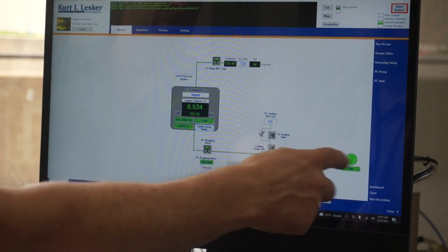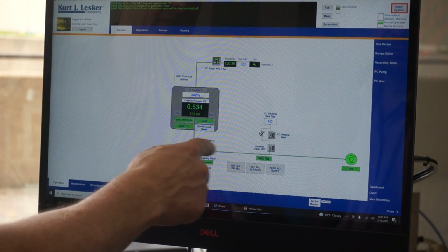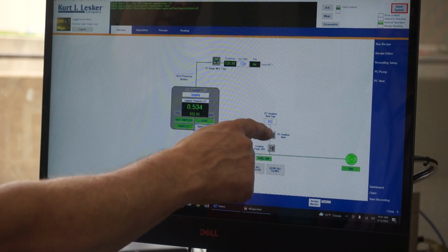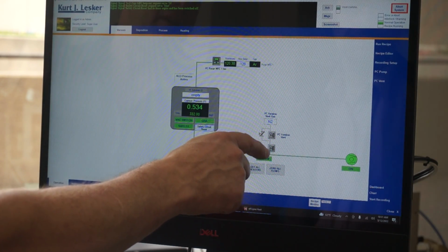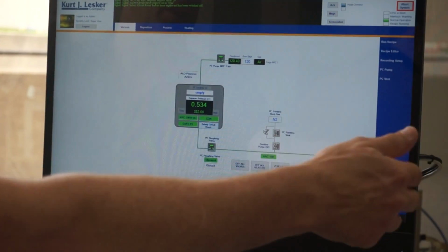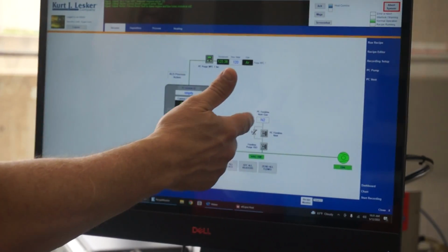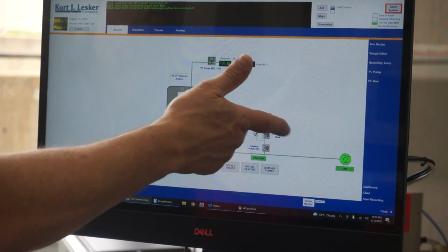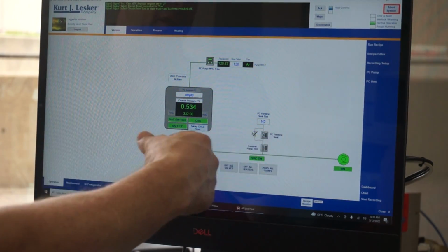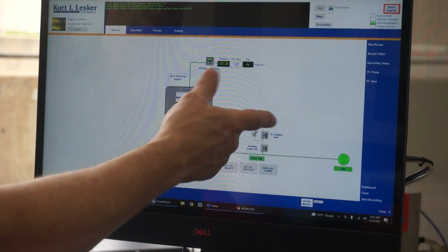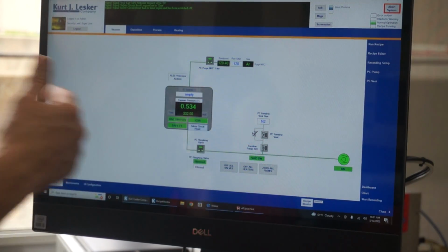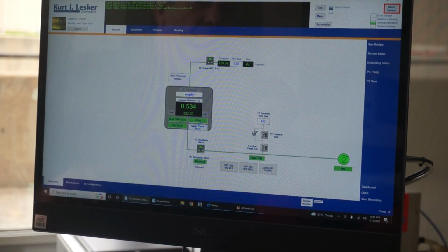And then you have the exhaust, the roughing valve, and the foreline. In the schematic, the PC foreline vent and a purge ISO, that was on the back side of the foreline. That's where your N2 comes in. That's really the only N2 that you have coming in here. This helps keep it clean. Your N2 will last a long time with this. You won't use very much at all.